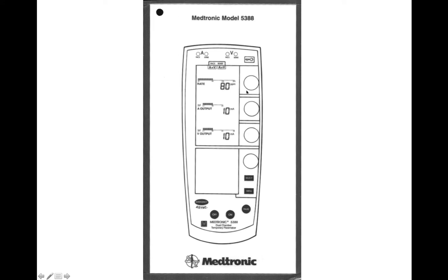Just familiarizing yourself with the main interface here — this is the lock button right here. This is the lock interface, which will keep you from making mistakes or somebody inadvertently changing settings. This is your pacing and sensing indicators for your atrial and ventricular outputs, so you can see what's actually happening on the pacemaker itself without having to look at the rhythm.